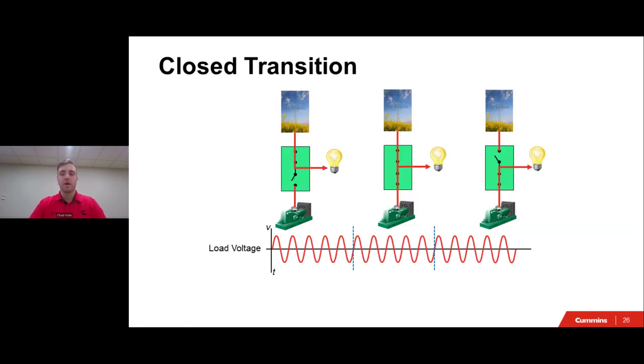Lastly, we have closed transition. So here on the graphic, you can see there is two sources that are live, your normal and emergency. At some point during this event, the automatic transfer switch notices that the normal source of power is fluctuating, so it will want to transfer power over to your emergency source. To do that, it will close on to the emergency source before opening to the normal side. This will lead to no interruption of power if, quote, if both sources are live.